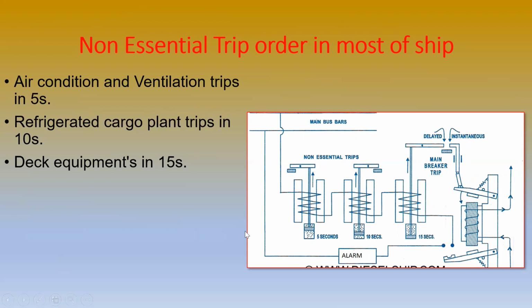This is a cylinder. The structure shown here is a cylinder containing silicone liquid, and a piston is kept in it. That is for the time delay. According to the movement of the liquid and the piston, with 5 second, 10 second and 15 second delays, the non-essential loads are removed. So the essential equipment will be provided with power supply. Under the overloaded condition, unwanted non-essential loads will be removed. Air conditioning is not required all the time, so we can remove it.